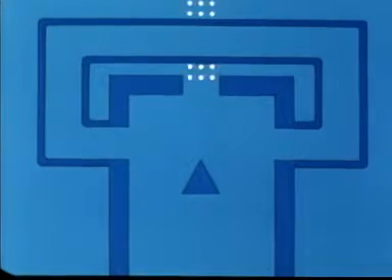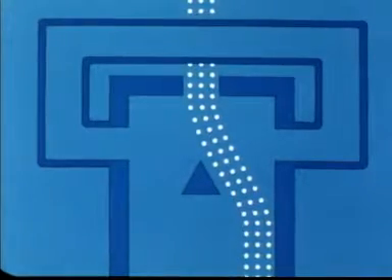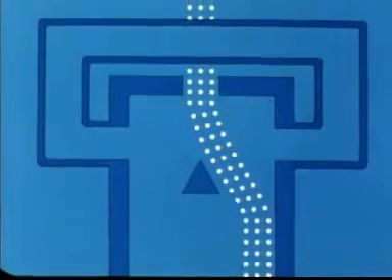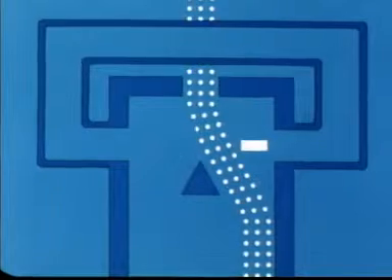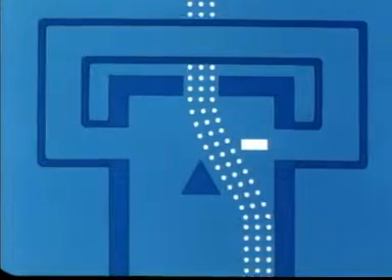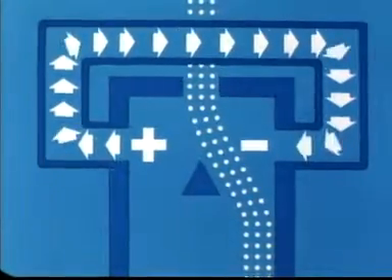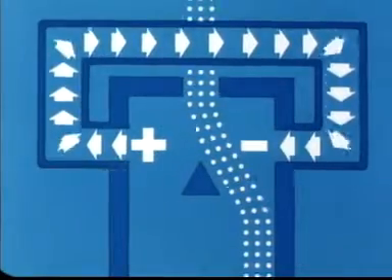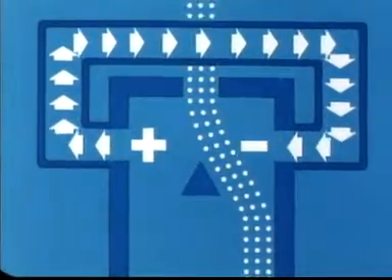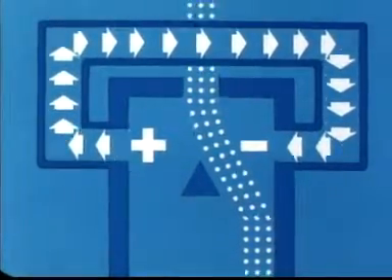When the flowing medium enters the meter, it must choose its path to the right or to the left of the splitter, since the center path would be unstable. The pressure at the wall along which the jet of fluid flows will then be lower than that at the opposite wall. Because of this pressure unbalance, some fluid from the higher pressure side will flow through the interconnecting passage to the opposite side. This flow of fluid is known as the control flow.